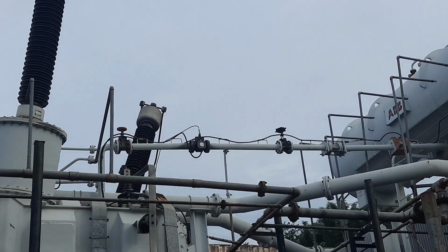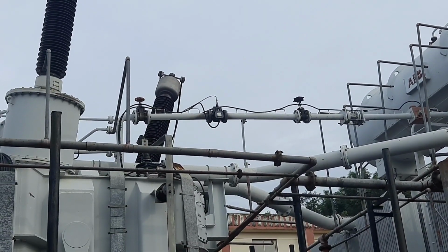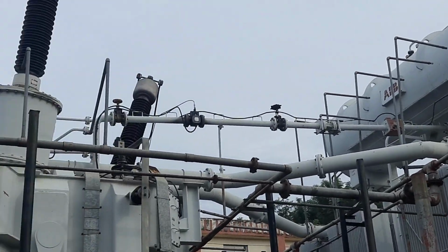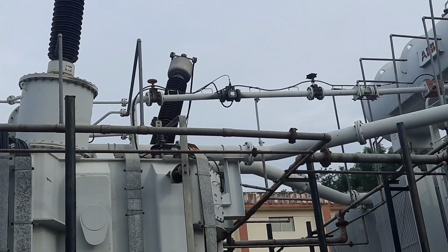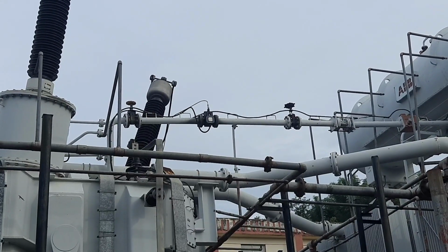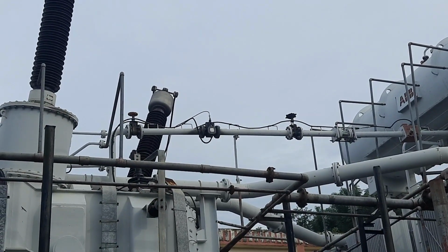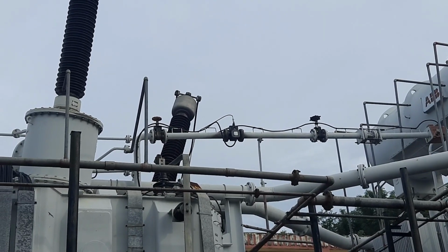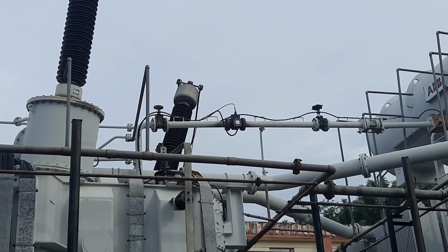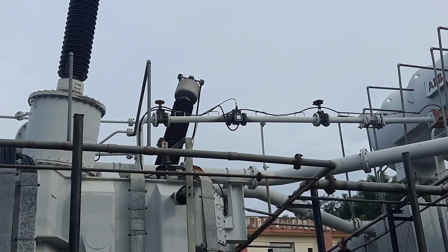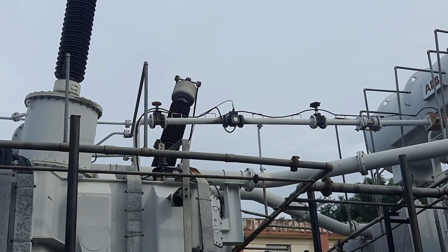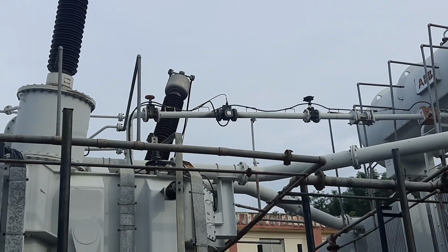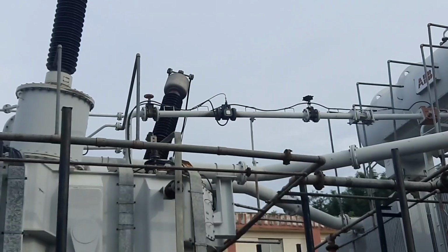So that is the purpose of this Buchholz relay, and where it is installed. You can see that is the conservator tank and the main tank. The installation of this is easy. When you look inside the relay also, you will have only 2 sets of NO contacts. The moment it is empty because of gases occupying the space and replacing the oil, both the contacts, one for alarm and one for tripping, will get activated.